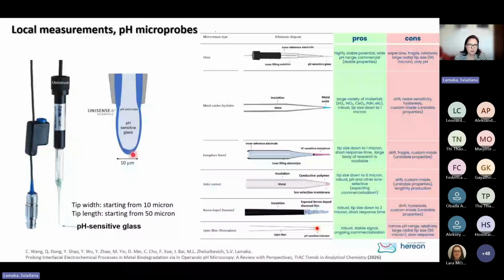And then if you want to go for a much smaller tip size, then an amperometric Clark type microprobe, also sensitive to the concentration of dissolved oxygen, is a very good alternative indeed. A small tip diameter from 3 to 500 micrometers you can choose for your application. These are commercial microprobes again, with very stable signal, very fast response. However, they are still microprobes, so they are highly fragile and very expensive. The principle is an amperometric probe, so there is a gold cathode inside the microprobe, and it's biased to minus 0.8 volts, so there is oxygen reduction on this gold cathode and a current is measured. Here there is a semi-permeable silicone membrane that only lets gaseous species pass to the gold cathode.